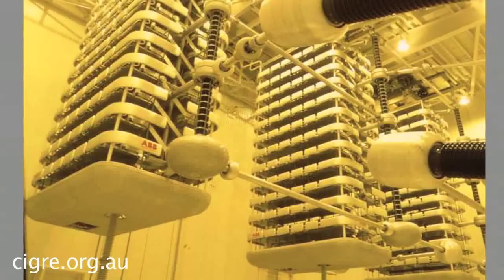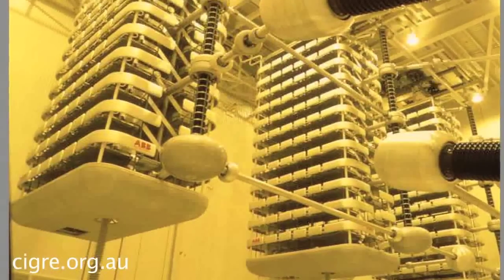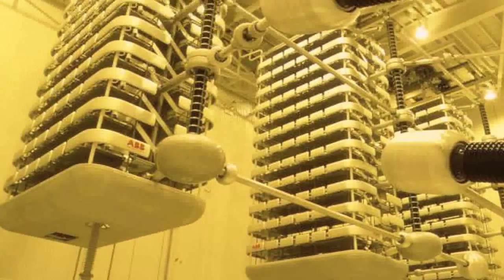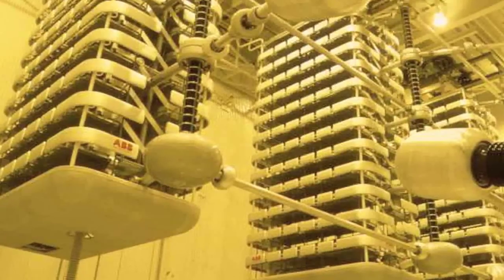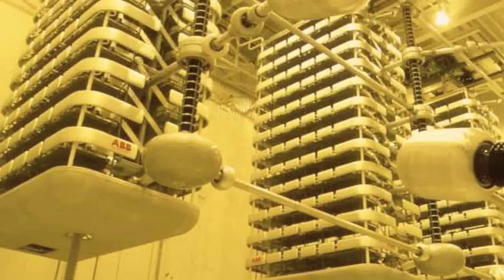To go forward, some years later I went to a DC committee meeting down in Brazil, and they showed us a movie of the fire they had in one valve hall. The whole pole — a whole valve hall, probably a 300 kV valve group — was suspended from the ceiling, very clever design. But the water cooling destroyed that whole pole. So we were somewhat vindicated, but they proceeded to improve their system and gotten away with it. The same thing happened to Siemens — I think they had a failure at Châteauguay, which was a frequency changer up in Quebec.